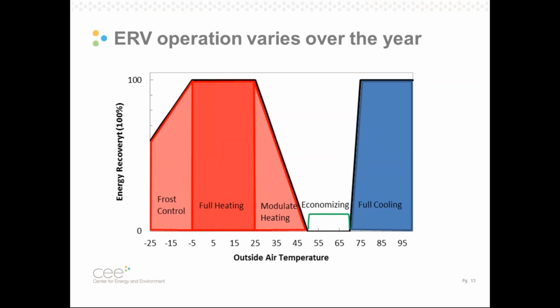So traditionally, energy recovery, I think, comes out of warm climates where they use it for cooling. So let's start there. When it's really hot outside, when the outside air has a higher temperature or greater enthalpy than the inside air, we're going to cool it down using the exhaust air. And in this situation, for high outside air temperatures, we're going to run energy recovery systems to do this.